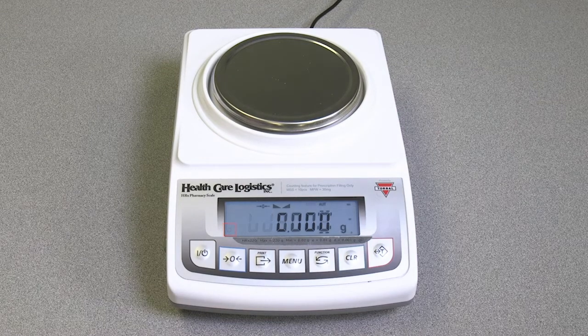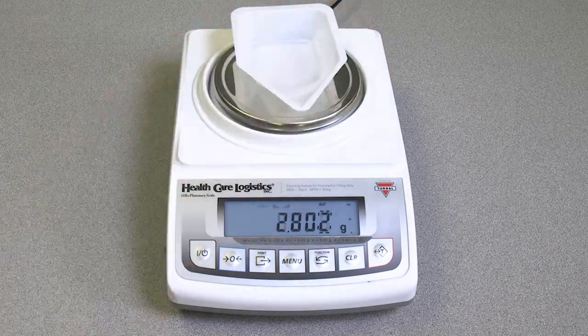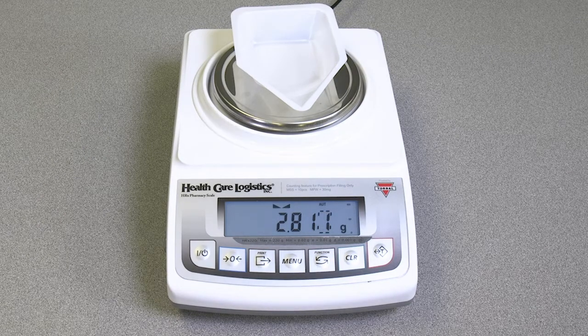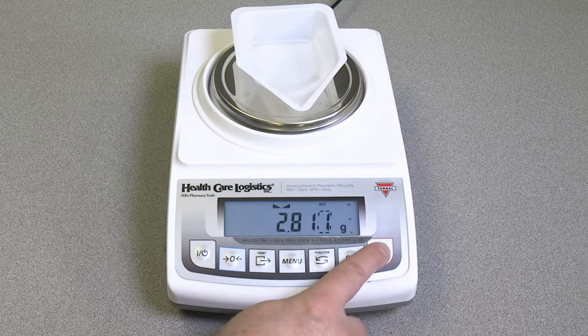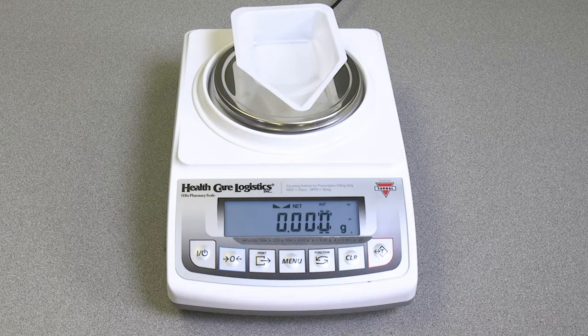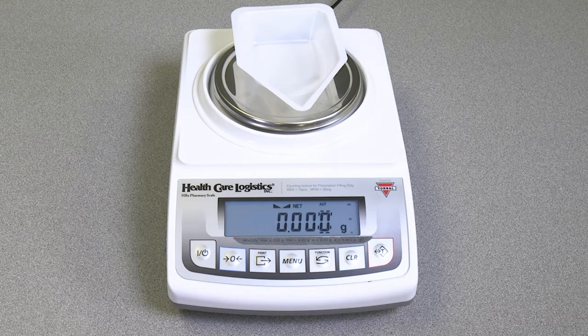After a few brief moments, the stabilization indicator should appear. The scale is armed with an auto-zero setting mechanism and automatically maintains a center of zero condition within plus or minus 0.5 milligrams. Still, the scale may be re-zeroed manually to obtain a new center of zero. We will discuss how to do this in a moment.